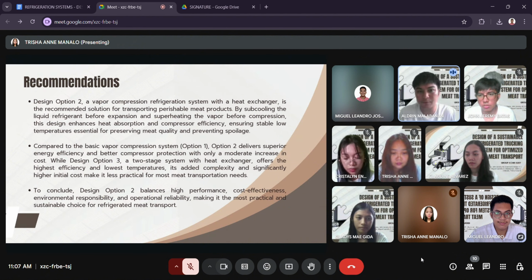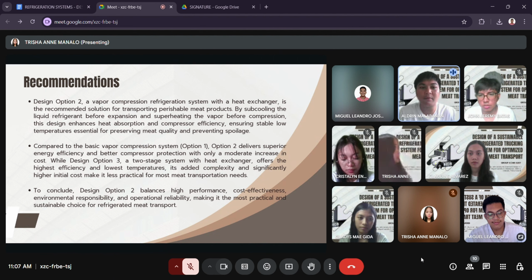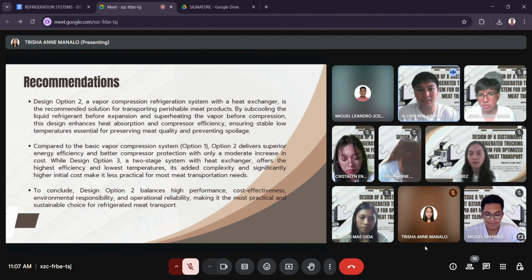Recommendations. Design option 2, a vapor compression refrigeration system with a heat exchanger, is the recommended solution for transporting perishable meat products. By subcooling the liquid refrigerant before expansion and superheating the vapor before compression, this design enhances heat absorption and compressor efficiency. Ensuring stable low temperature is essential for preserving meat quality and preventing spoilage. Compared to the basic compression system, option 1, option 2 delivers superior energy efficiency and better compressor protection with only a moderate increase in cost.